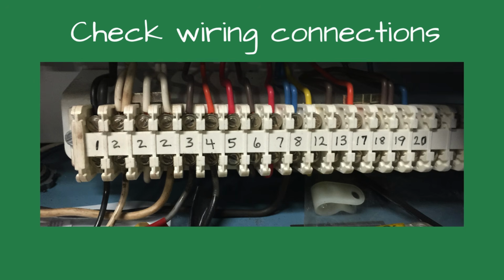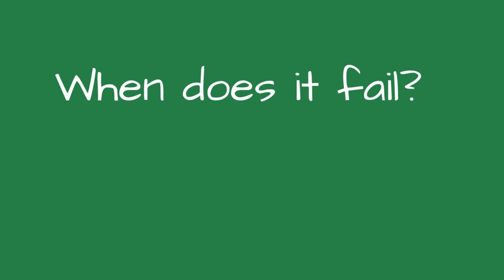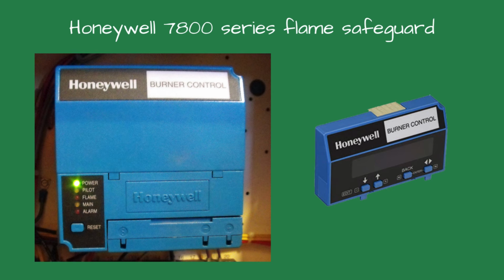Check all wiring connections. Loose or corroded terminals are the number one cause of intermittent issues. Tug gently on each wire, reseat and tighten as necessary. Determine the failure stage. Ask the owner, does it fail while trying to light the pilot or after the main burner is on? If the boiler is equipped with a Honeywell 7800 series flame safeguard, you can use a digital display to view flame failure history and the last fault code.